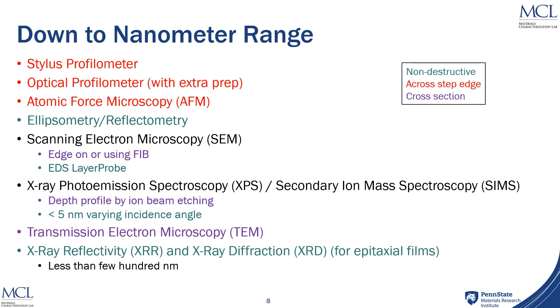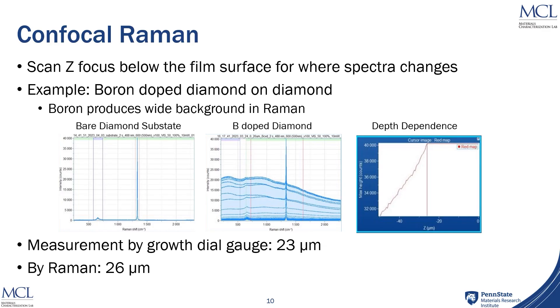Let me give you some examples from real materials. The first example is confocal Raman. Here you would be looking for the Raman signal as you scan the Z-focus below the surface of your film into the substrate. An example here is boron-doped diamond on diamond — this would normally be an extremely difficult thing to measure. On the left we have a Raman spectrum of what a bare diamond substrate looks like; in the middle, what the Raman spectrum of boron-doped diamond is. As you scan the Z-focus through the material and watch the changes in the spectra, you can see where the boron signal in diamond starts to decay and use that to measure where the end of that layer is. For this sample, they used a dial gauge to measure the surface of the substrate and then after depositing the film got a thickness of about 23 microns. By using confocal Raman, they were able to measure a thickness of about 26 microns.